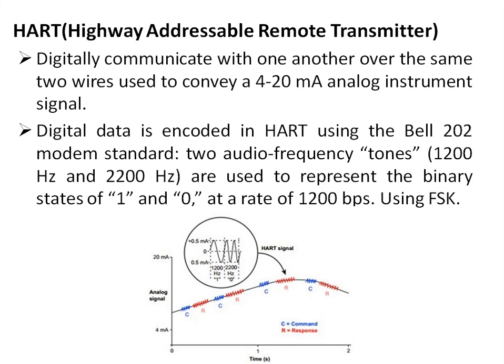In addition to voltage conversion, the resistor is also required for HART communication. HART is one of the field bus protocols supported by all transmitters. HART uses the same two-wire conventional 4 to 20 milliampere signal for transmitting digital data, following the Bell 202 modem standard. It transmits digital 1s and 0s using two audio frequency tones: 1200 Hz for binary bit 1 and 2200 Hz for binary bit 0. Data is transferred at a rate of 1200 bits per second using frequency shift keying (FSK).